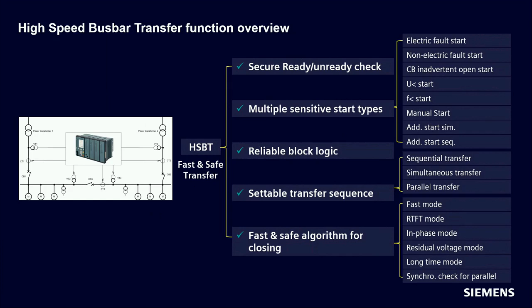We can start the transfer manually, or we have some additional start types which can be, for example, combined with some protection function, for example, the reverse power protection. So then we have a reliable blocking function for this functionality. If we have a fault on the motor bus, then of course we have settable transfer sequence: sequential transfer, simultaneous transfer, and the parallel transfer. And in the end, we have the fast and safe algorithm for closing the circuit breaker, as I explained in the slide before.